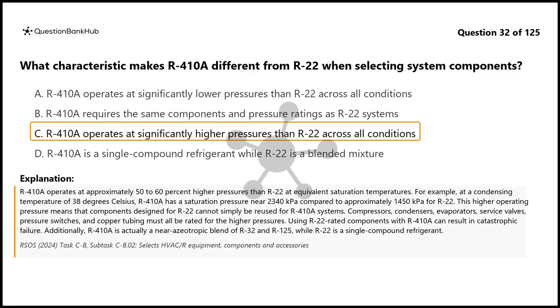Compressors, condensers, evaporators, service valves, pressure switches, and copper tubing must all be rated for the higher pressures. Using R-22 rated components with R-410A can result in catastrophic failure. Additionally, R-410A is actually a near-azeotropic blend of R-32 and R-125, while R-22 is a single compound refrigerant.